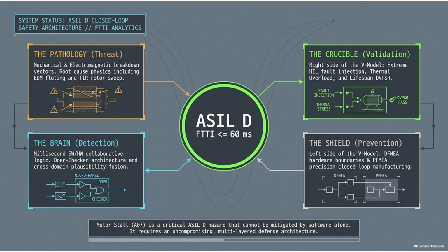But the terrifying part is, it isn't just one strike. Because it's switching thousands of times a second. Exactly. Because the inverter is switching thousands of times a second, this lightning storm is continuous. This is the electrical discharge machining part. The EDM. Right. Every single microscopic lightning strike blasts a tiny, tiny crater into the hardened steel of the bearing. Over thousands of miles of driving, this plasma cutter effect creates this washboard pattern on the metal, an effect engineers call fluting. So this invisible lightning is literally machining away the hardened steel while you're just commuting to work.